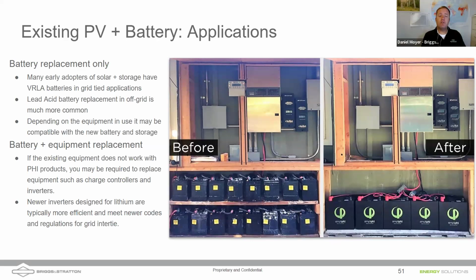Back in our lead acid battery days, and even still now, we'd talk about depth of discharge being one of the main factors in a battery not lasting as long, and that's true. But one thing impacting lithium ion batteries even more is the C-rate at which we charge or discharge. The harder you work the battery, even at just 80% depth of discharge, that can be another contributing factor to shortening battery life.